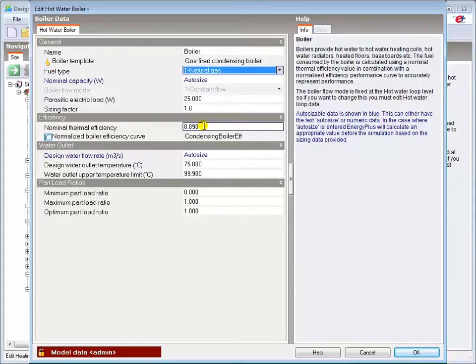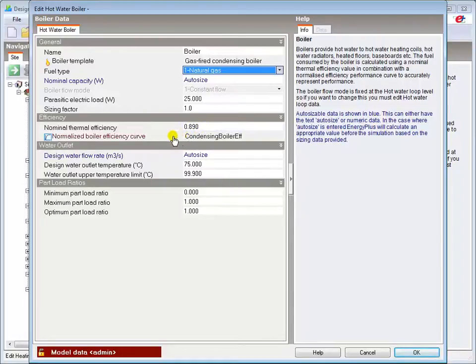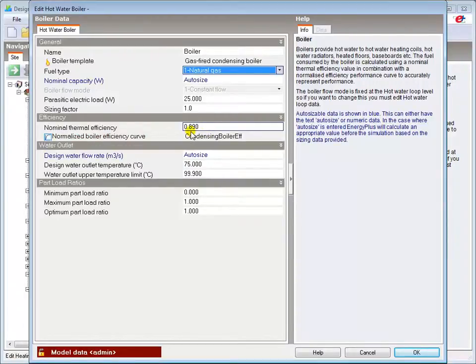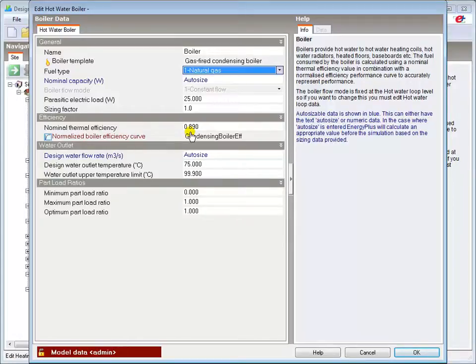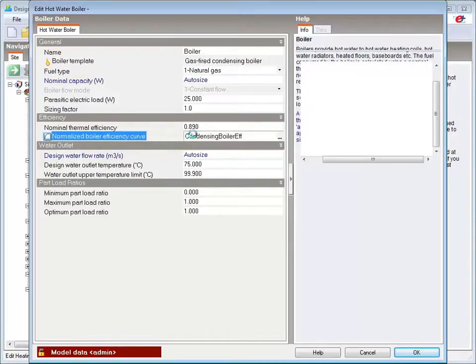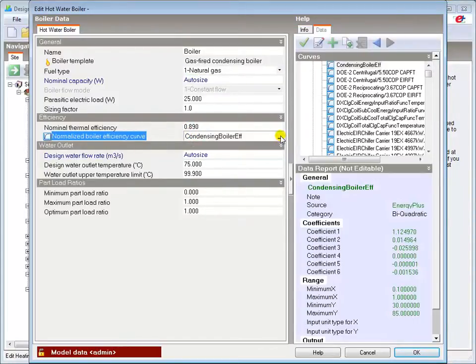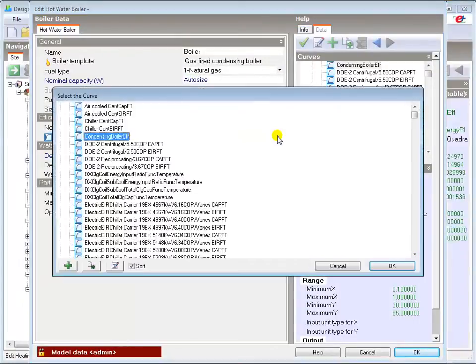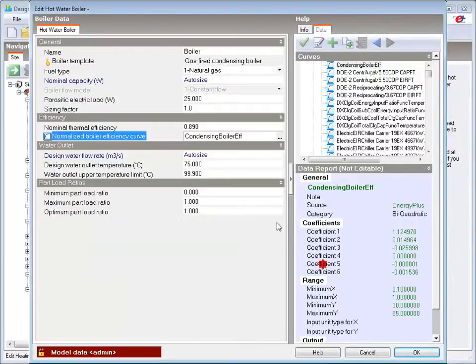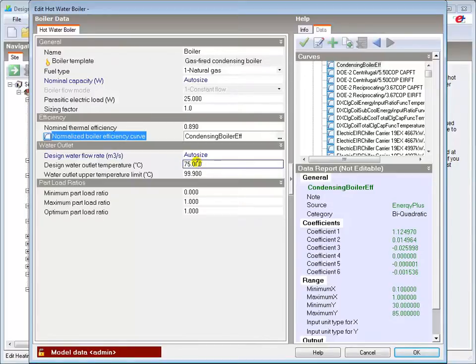The nominal efficiency value entered will be used with the boiler efficiency curve and temperature data to determine the operating efficiency at each time step. A relevant boiler efficiency curve is loaded by the boiler template, which will be sufficient for most modelling needs. Other curves are available, and you can create and load your own if required.